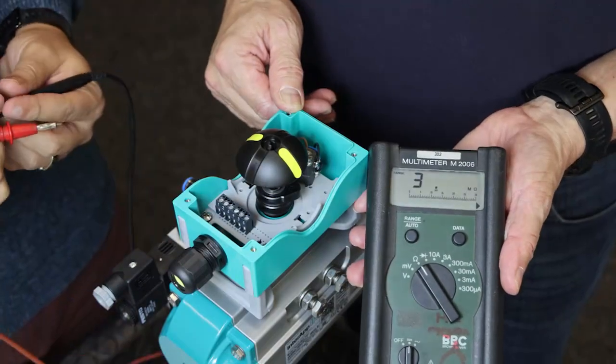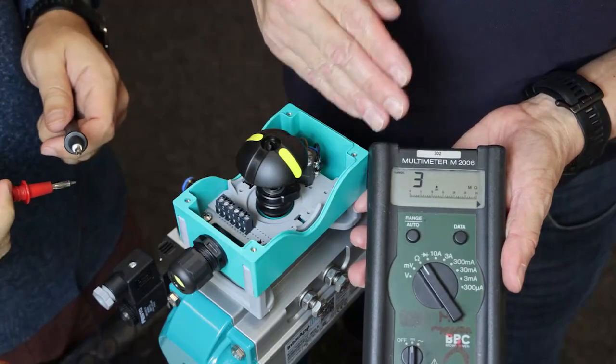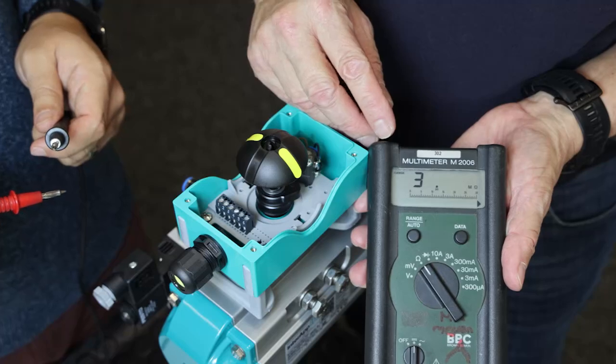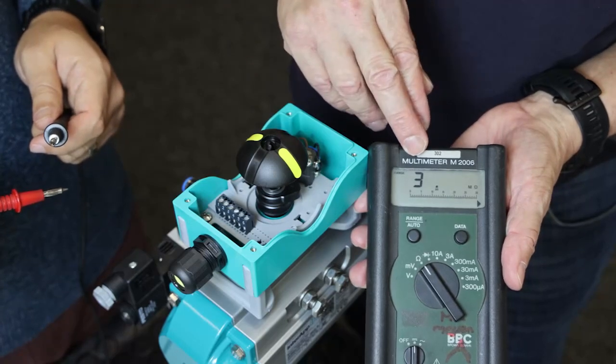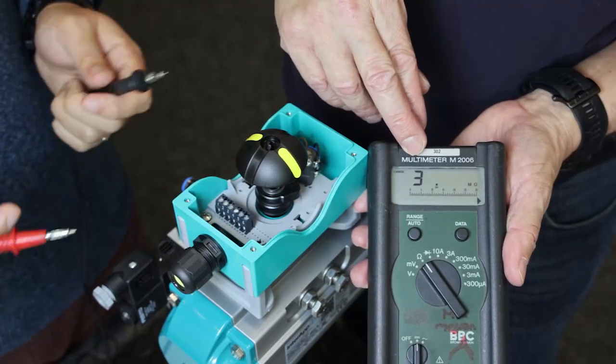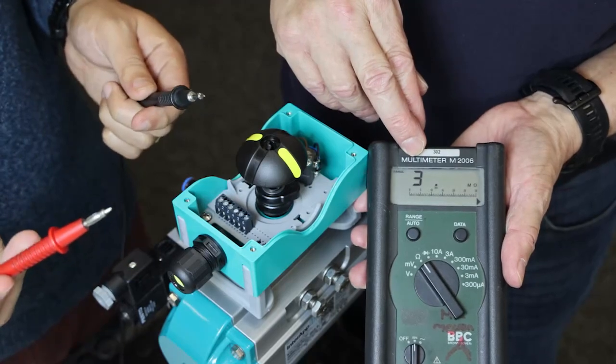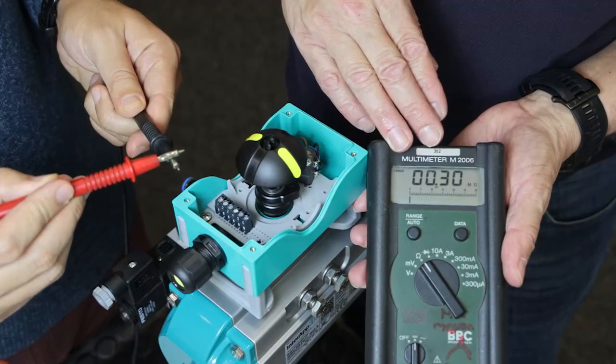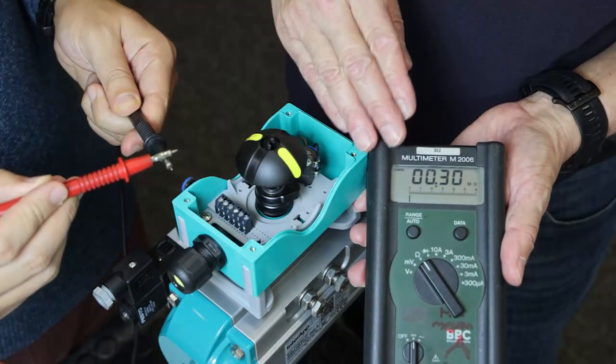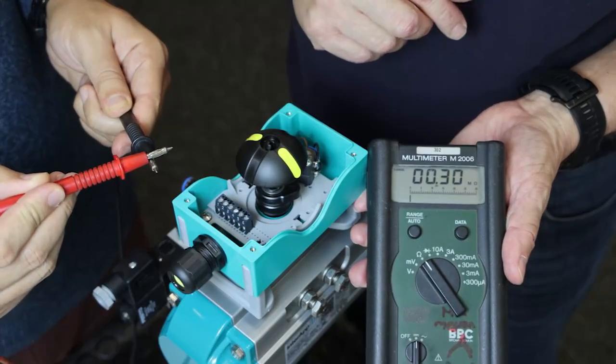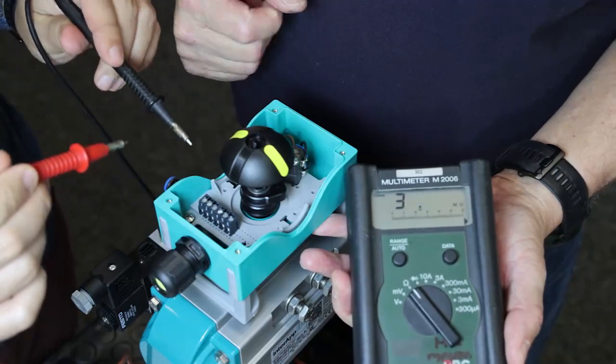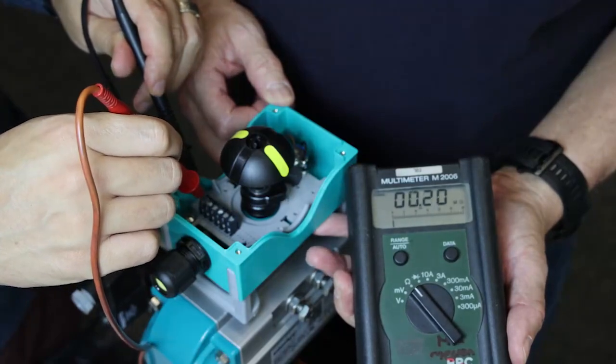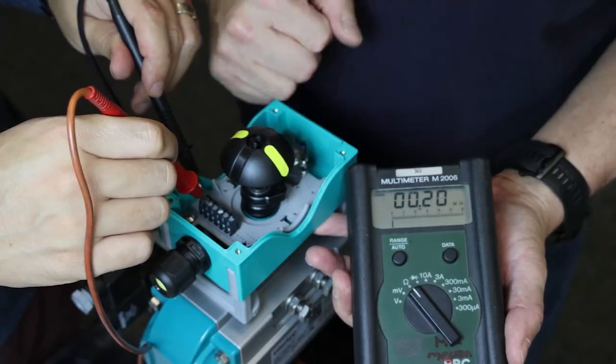To control the connectivity, we use a multimeter to measure the resistance. Here you see, we have a very high resistance which means we have no contact. When we connect both together, the resistance falls to zero and we have contact. Now we check on terminals one and two. We have connection for the closed position.